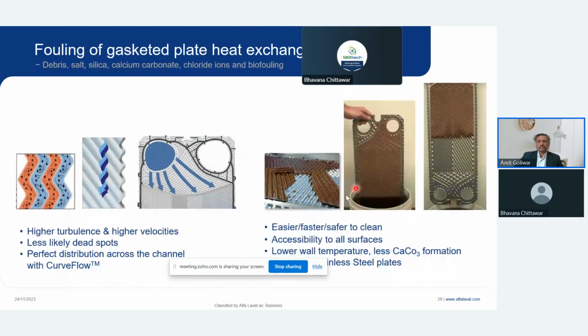Also, if you do not size the heat exchanger properly, you come across this kind of scale formation. If the velocity and turbulence are not properly maintained, there are such scale formations. So it is very important that the PHE or any heat exchanger is sized properly. It is not necessary that an oversized heat exchanger, or one with more area, is better. More is better is not the formula. Efficiency should be the selection factor.